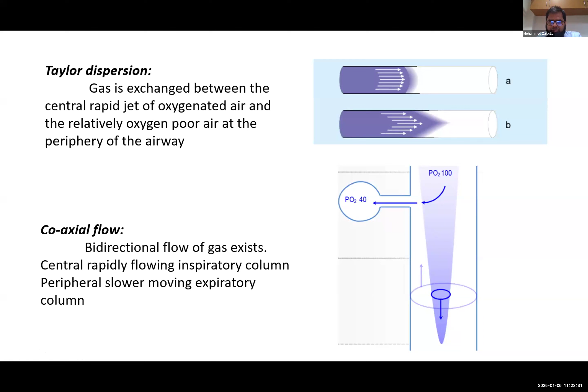Because of the oscillation of this piston pump and friction, there will be a lot of gas exchange through this direct bidirectional flow. The central core of oxygenated air goes through the core of the major airways, and the periphery of the airway carries the expiratory gas outwards. These two mechanisms, in addition to the other mechanisms we discussed in the previous slides, will play a major part in the gas exchange mechanism.